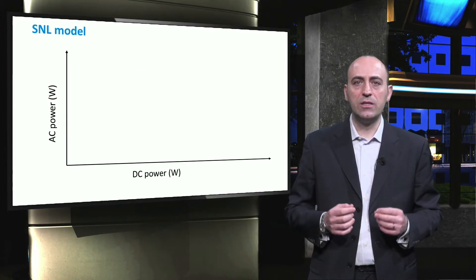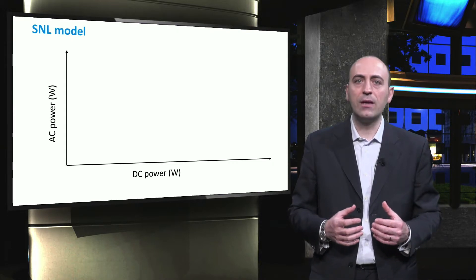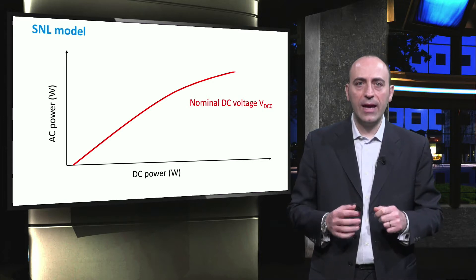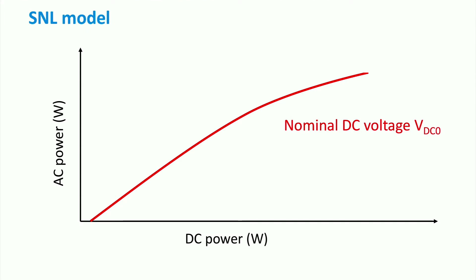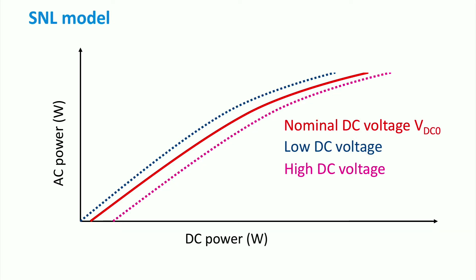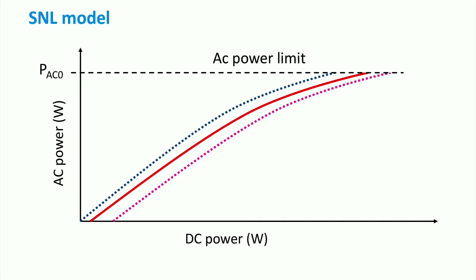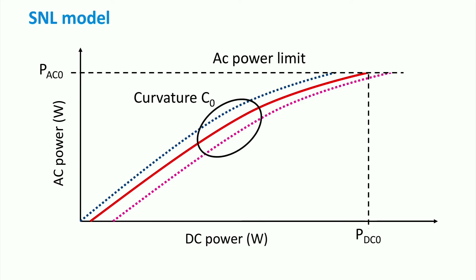With the SNL model, it is possible to define some parameters that help describe the efficiency. Let's consider a device working at the nominal voltage VDC0. It is possible to notice that the pattern changes whether we work with a lower or a higher voltage. It is important to underline that in the graph shown, the non-linearity of the input-output behavior of the inverter is emphasized. The AC power limit for which the inverter is designed is PAC0, and it provides the nominal DC power PDC0 when it crosses the nominal voltage line. The curvature C0 is the parameter used to describe the non-linear nature of the inverter characteristic. Additionally, other parameters are usually provided such as PS0, which is the self-consumption of the inverter, and the PNT, or night tare, of the inverter.